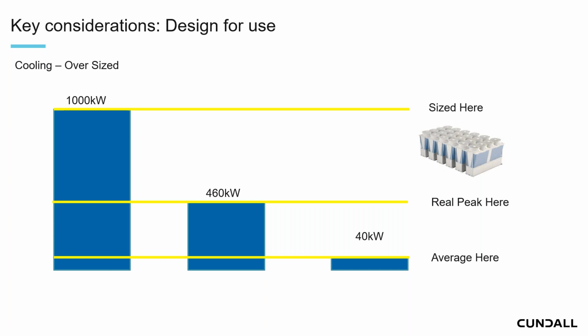Most plant - chillers, boilers, fan coil units, heat pumps - generally operate mostly in the range of 20 to 30% of their peak. We need to look at how efficient the equipment is at those low ends, or use modular equipment so we can control it more effectively. It's really about how we control and use different pieces of equipment for every hour of the year, and understand how to size them more appropriately to their actual use.